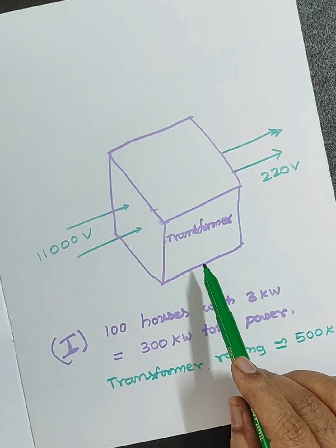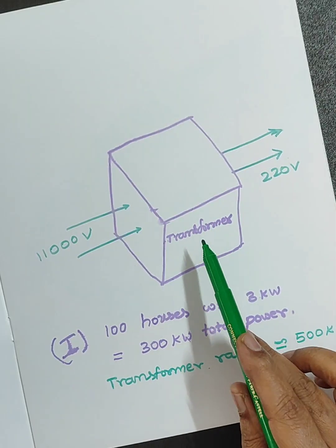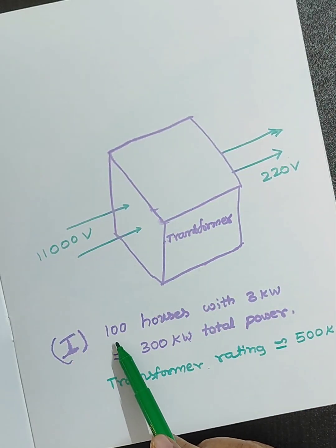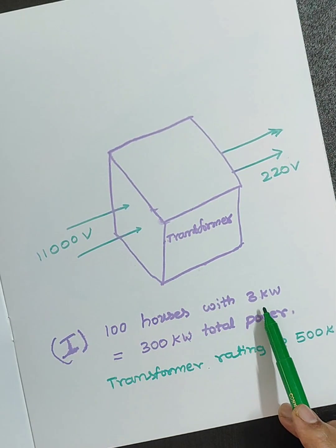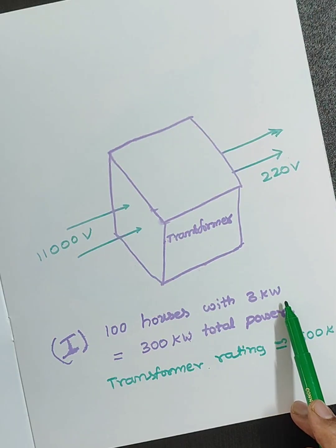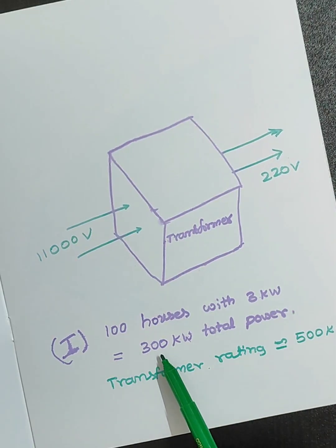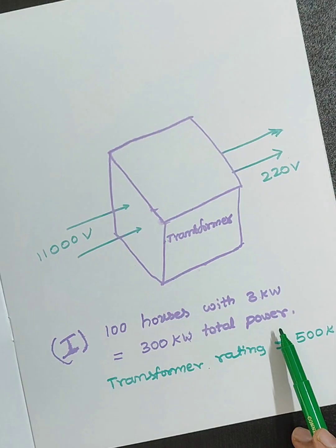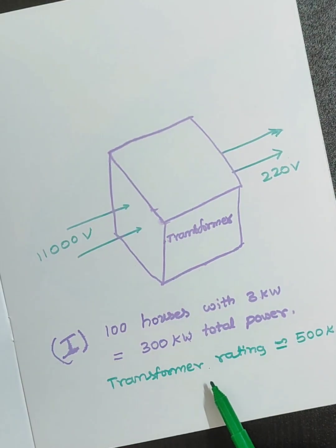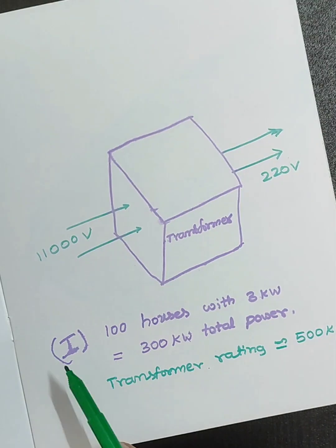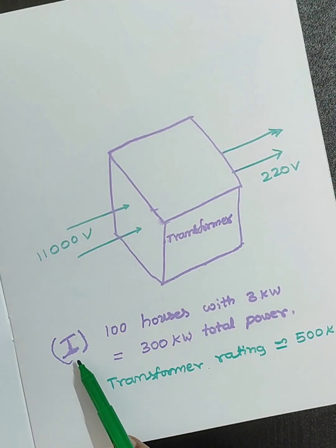Now, the scenario is: initially when they put the transformer, say there will be 100 houses with 3 kilowatt capacity each, that will be 300 kilowatts total power. Normally they will put the transformer rating much above that, say 500 kilowatts. This is the first type of problem that can occur, and it is normally happening.